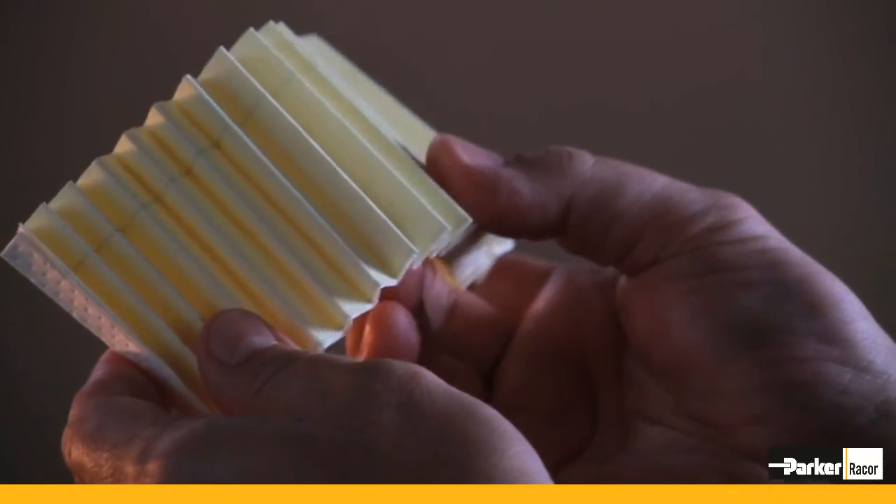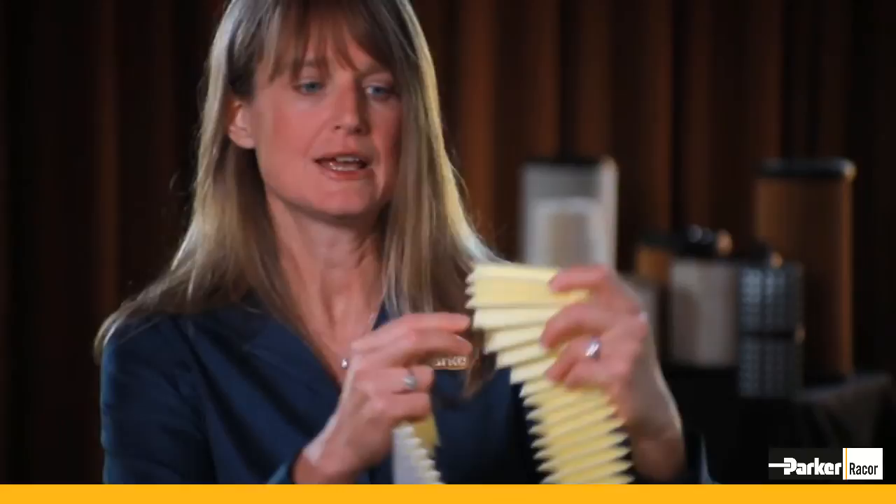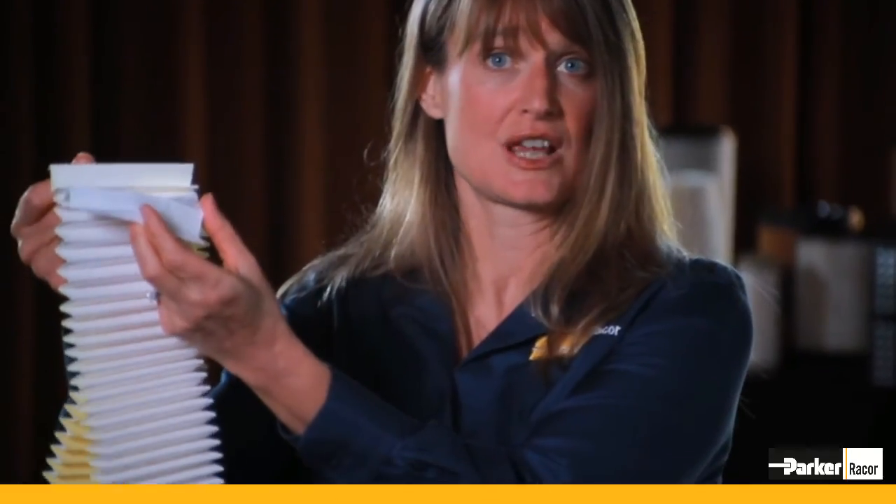Whereas in the past we had particle fibers on the order of a micron, we're now pushing down into the micro and now into the nanofiber region. As filter dimensions decrease, the demands for filter paper become more extreme. We have therefore moved to composite-type media — a structural support layer providing both structural support and fine particle filtration, composited with melt-blown synthetic layers. This four-layer media is designed so each layer marries with the others to hold dramatically higher amounts of dirt compared to base paper alone.